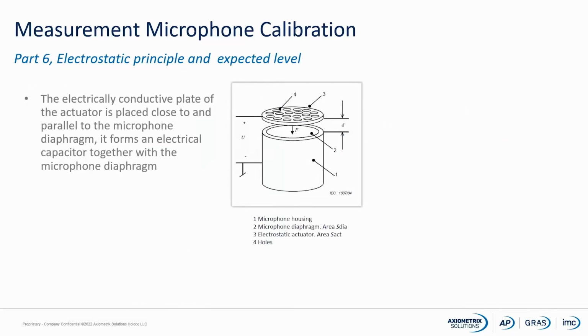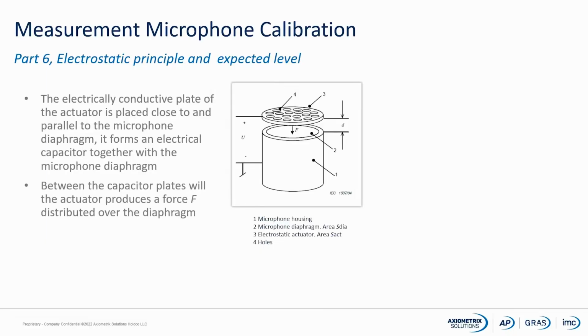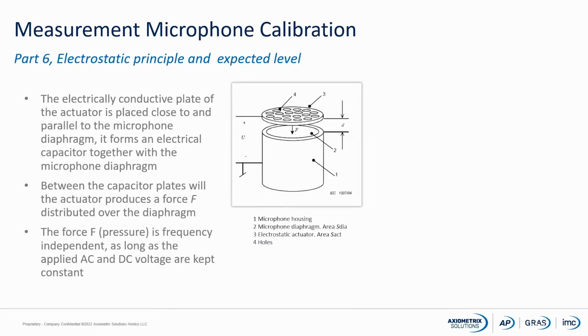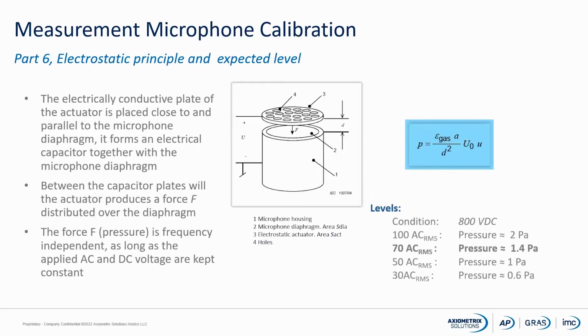Let's have a closer look at how it works. See the plate we have in our actuator, the one here with the holes; together with the diaphragm of our microphone it will be a condenser, a capacitor. So we have these two parallel plates making a capacitor, and between these two plates we will build up a force which will make the diaphragm move. The force or pressure is frequency independent, as long as the applied AC and DC voltage are kept constant. That's the formula for how to do the calibration or find the pressure.